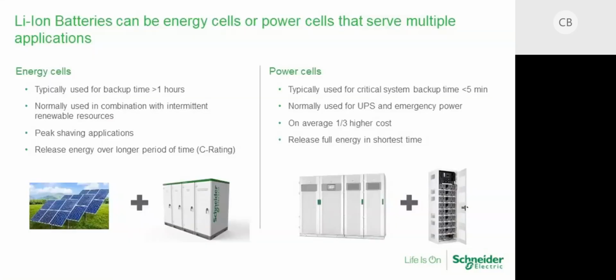Now, I want to give you a brief overview. Before we go into the product itself, I want to highlight a few differences between what we call energy cells and power cells. On the right-hand side, a power cell is typically what we see in a UPS. Number one, they're designed for short run times, and they can discharge their entire capacity of energy in a very short period of time. That's why we call them a power cell. They're normally used for UPS and emergency power backups. In comparison to energy cells, lithium-ion power cells are about one third higher in cost, since a power cell has a different lithium-ion chemical composition.